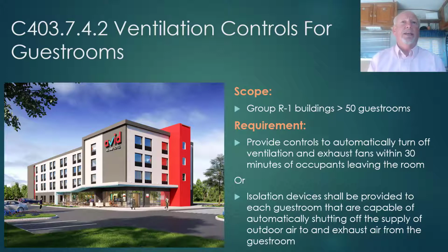It makes no sense to reduce the heating and cooling, but allow the exhaust fan to continue to waste fan energy and conditioned air when nobody's in the room. Now, if you've got an independent exhaust fan serving that room and you have that controlled by an occupancy sensor, that's great. You comply with the requirement. If you've got a central exhaust system, you're going to have to provide some isolation devices to each guest room that are capable of automatically shutting off the supply of outdoor air and exhaust air from the guest room when it is unoccupied.